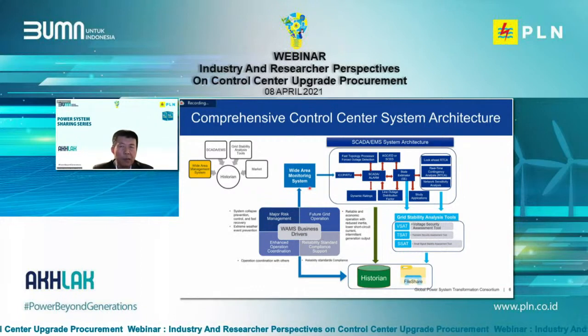For example, the inertia - do you need to estimate the inertia in real time? PMU could fit that role very well. PMU is also really good for islanding detection and system restoration. We'll have a more detailed discussion on this in the future, but to summarize: when you kick off a PMU project, you need a very clear use case and the order in which you can put it online over several years. This is not as quick as EMS, to be honest, because EMS is a model-based solution, while this is a measurement-based solution that takes more time to validate the results.